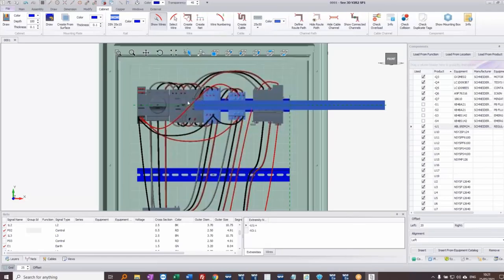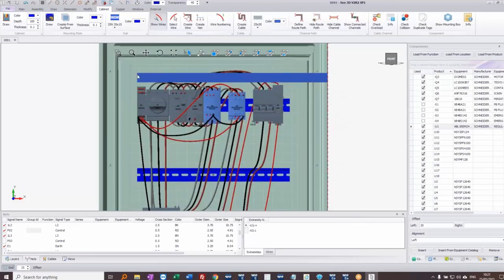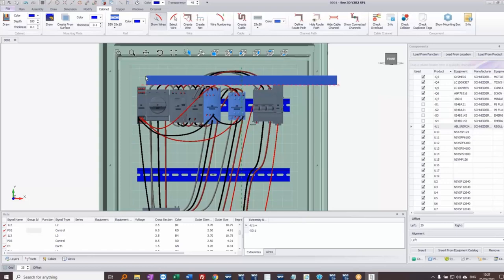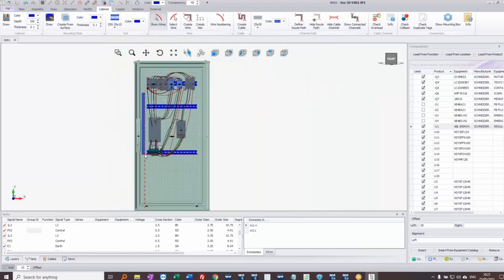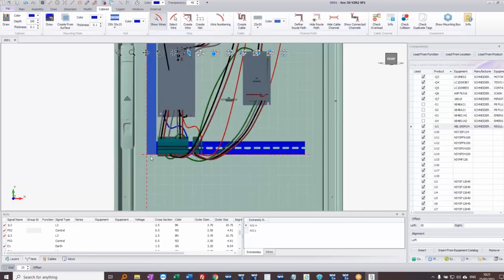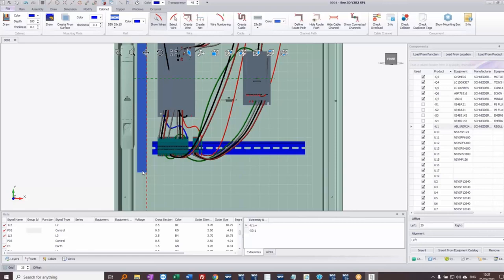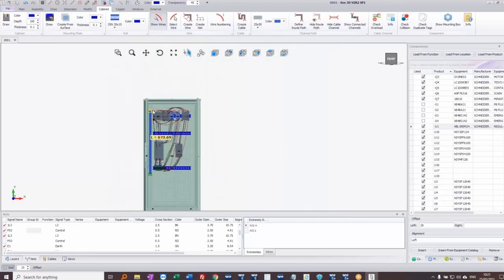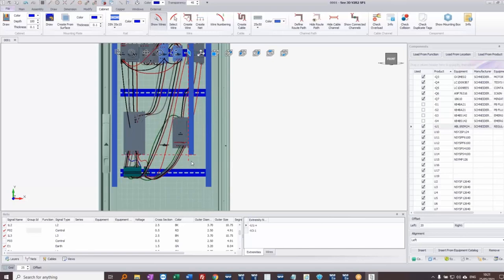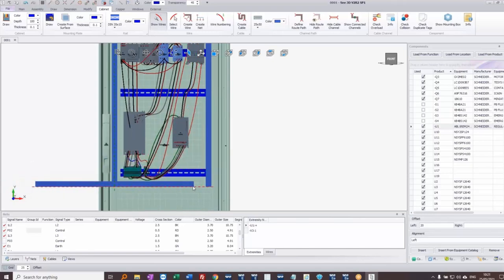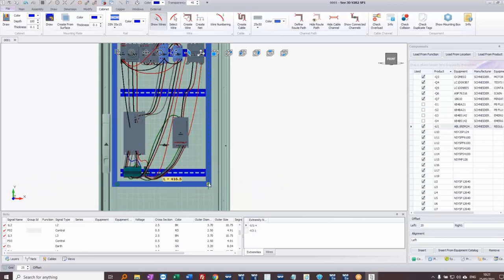Under predefined channels, I'll pick some wireways — 25 by 50mm — and get a piece I can place on the drawing. I'll press Z to orient it vertically, drop it down the side first, then use the handle to pull it to the top. I'll add one on the right-hand side, then place another going across from the left — pressing Z again to change orientation and adjusting the length so it joins nicely.